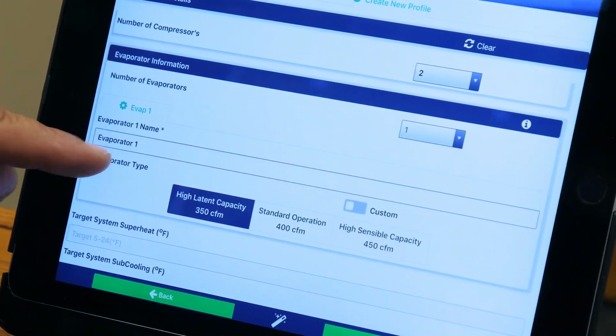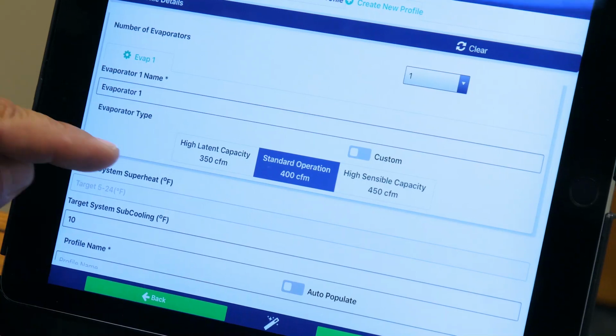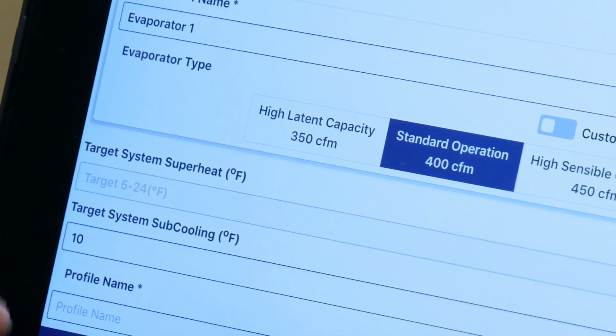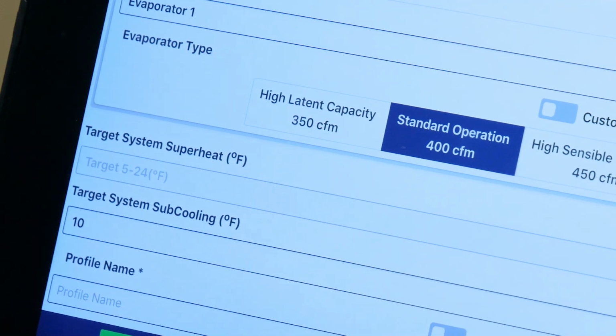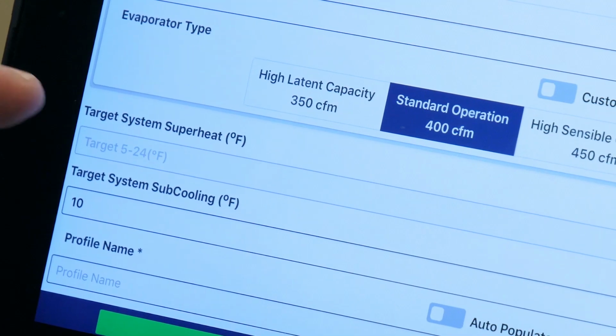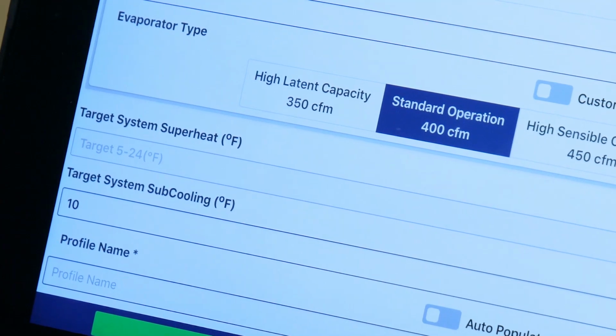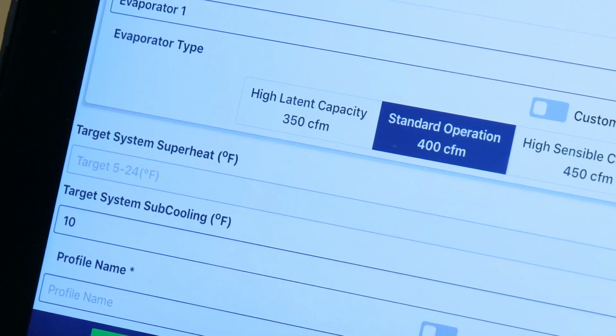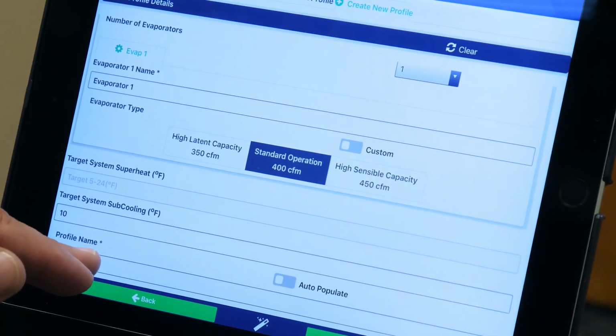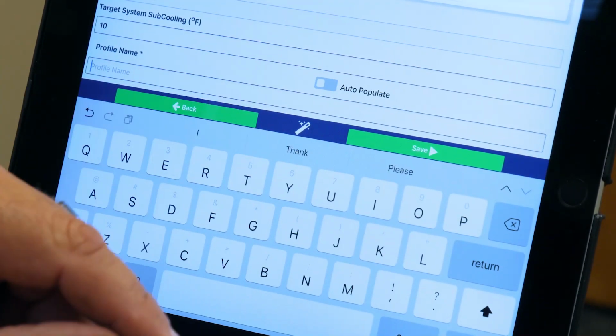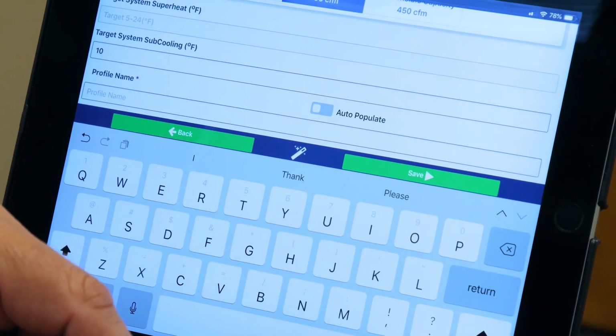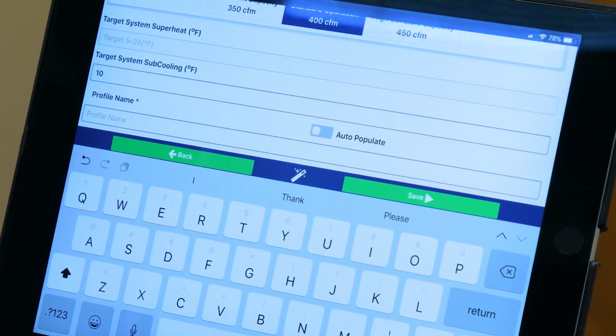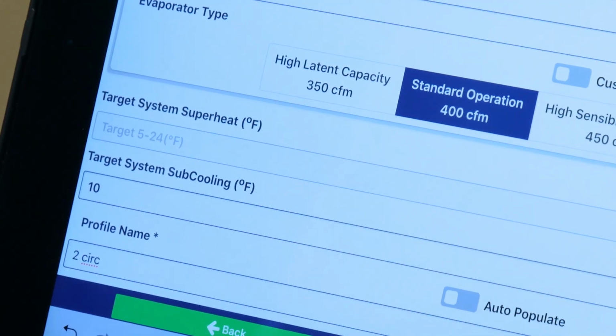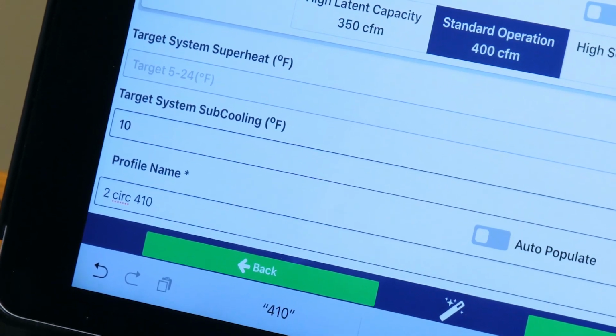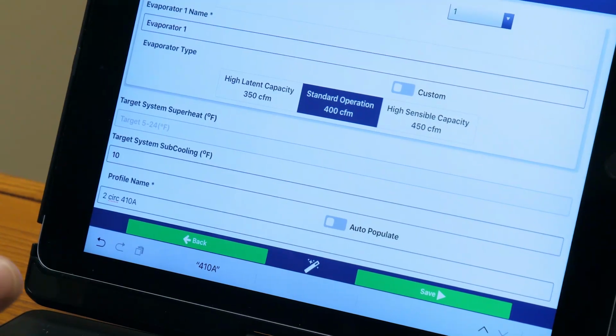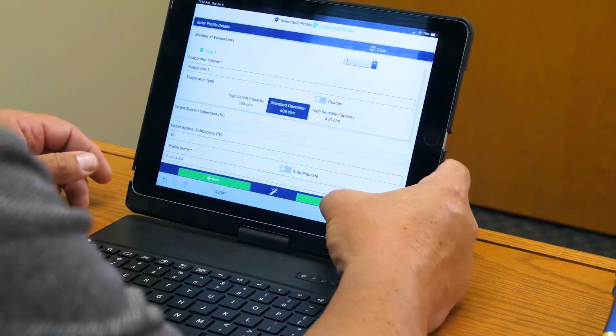Evaporator information, 1 evaporator. Standard operation. System superheat is calculated. Our system subcooling, we're going to leave that at 10. Just so you know guys, we put our superheat and subcooling at 12 and 10 just as default. That will pretty much make any setup happy. Now we're going to go ahead and name this profile. We can type in a name or we can auto-populate. I want to really be able to identify this, so I'm going to type in 2 circ 410A. I'll just leave it at that. Once everything's set up, you simply hit save.